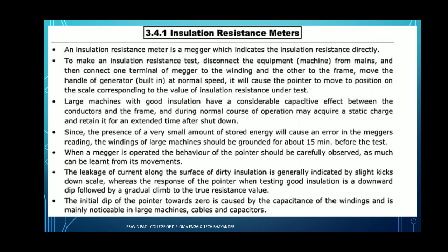Since the presence of even a very small amount of stored energy will cause an error in the megger readings, the winding of the large machine should be grounded for about 15 minutes before the test.